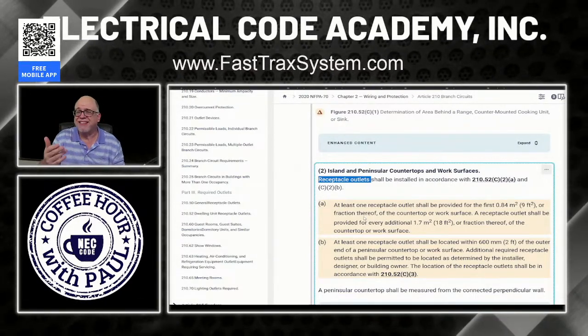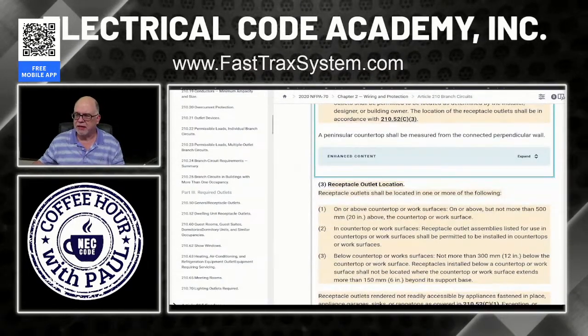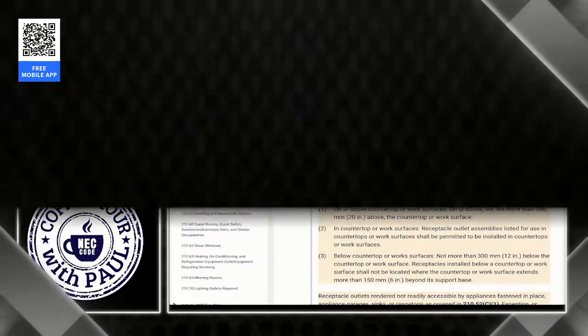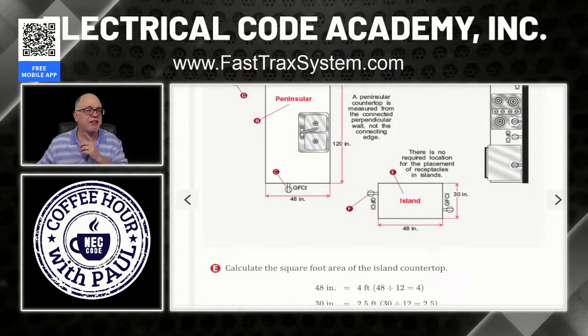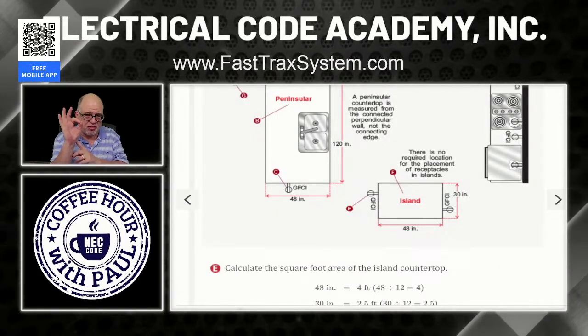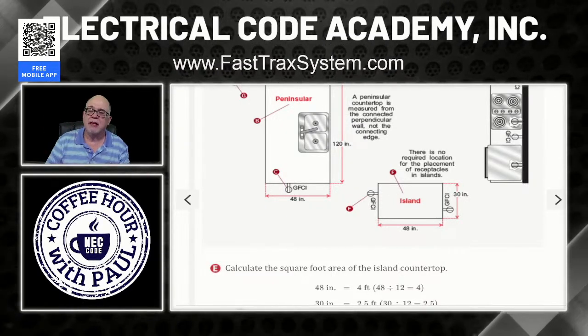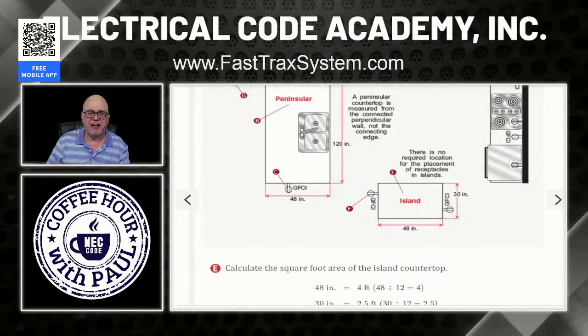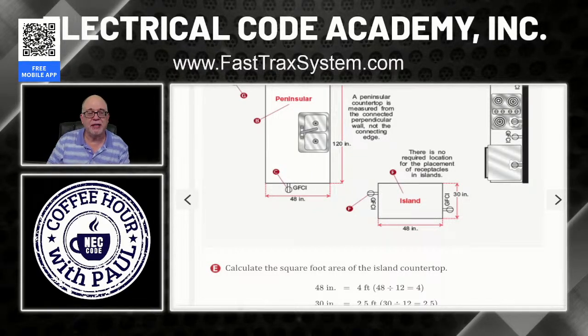Why would I say that? Because basically, if I had this peninsula right here, let's come back real quick. And this is why I do this. If I had this peninsula right here, could I put a simplex receptacle, a single receptacle, in there and still be compliant? Absolutely. Because it's all about the receptacle outlet box, not the device that I'm putting into it. Duplex, fine. Simplex, fine. Probably going to always put a duplex in there, but you get why I make that distinction.